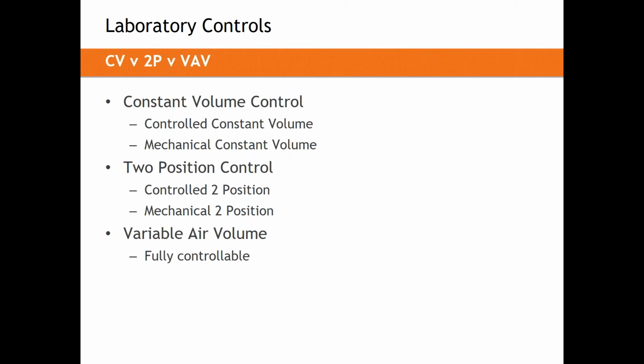If you take a VAV box or a high accuracy terminal and control it and hold it to a constant volume, we call it a constant volume device. However, the equipment we need to do that is still full VAV. It's a controller, an actuator, and a transducer doing all of that work of maintaining a constant volume. So we call that controlled constant volume. So this is where we have to separate closed loop valves and open loop valves. With a high accuracy terminal or VAV box, you can achieve controlled constant volumes. However, on a Venturi valve, on an open loop device, we can achieve mechanical constant volume.